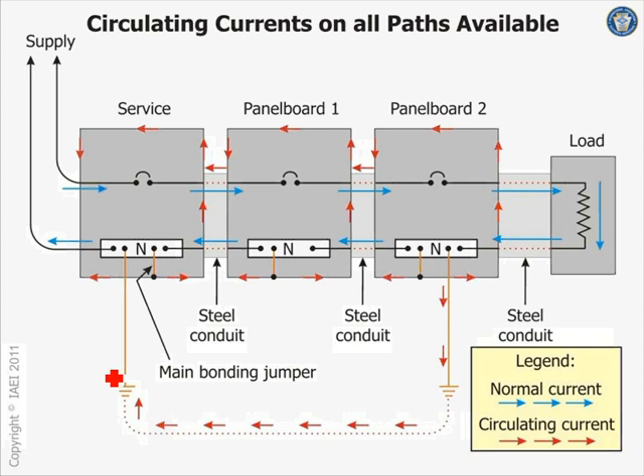Say it's a 20 amp circuit going to that equipment, or higher. You might have 30 pieces of IT equipment inside the rack, and each one of them is tied to ground, and then that steel rack is sitting on concrete, so you have that problem. Now, tied to ground is one thing, tied to neutral is a completely different thing.